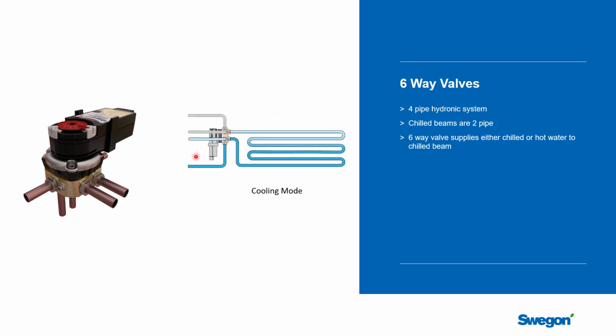So how do these work? Well, the reason they're called six way is there's 6 connections to them. So right now you can see where the building loop chilled water connections are right here. The other 2 pipes that are grayed out are actually the hot water connections, and this beam is in cooling mode. So what it's allowing is it's drawing water off of the main loop, allowing that to go through the coil. All the coils for all the chilled beams that are on this would be 2-pipe chilled beams. Even though you're going to be able to heat and cool with them, every tube in that chilled beam is going to be used in one water circuit, and when you looked at the beam, there'll only be one set of connections on it.